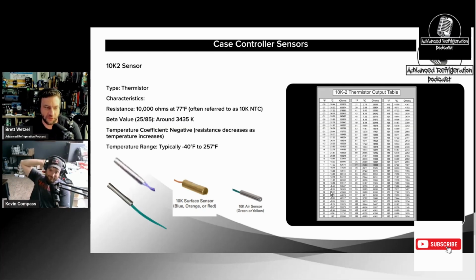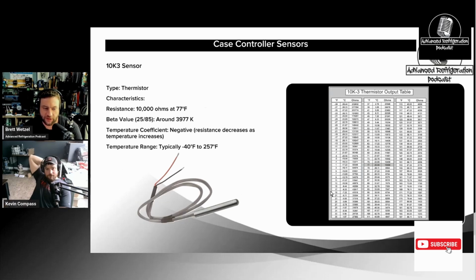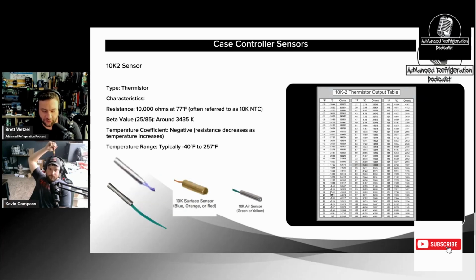So you have the 10K2, which is on the CPC, which is on Micro Thermo, and then you also have 10K type 3. Now, whenever you hear the first number, the 10K, that typically represents the amount of ohms at 77 degrees if it's an NTC, right? So no matter what, if you measure it at 77 degrees, you will get 10,000 ohms at that temperature. But the problem is that the curve changes.